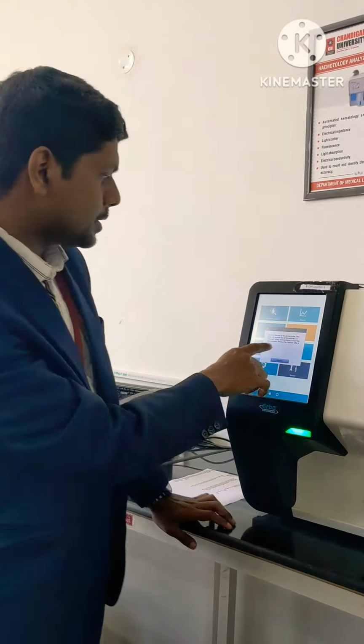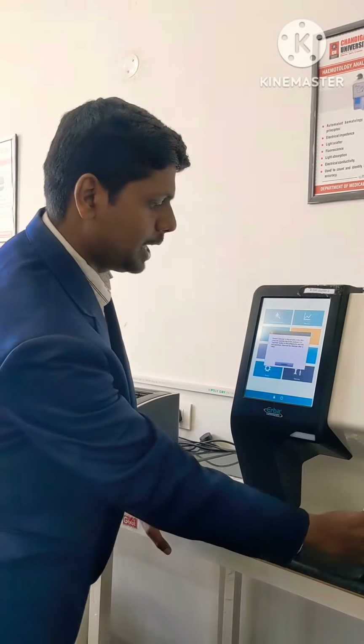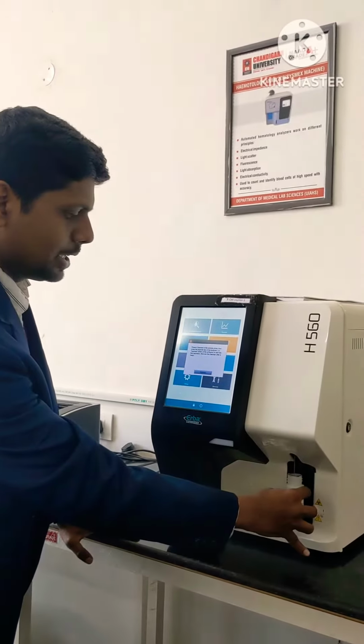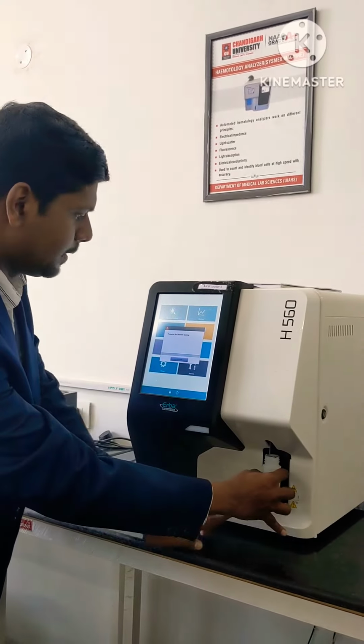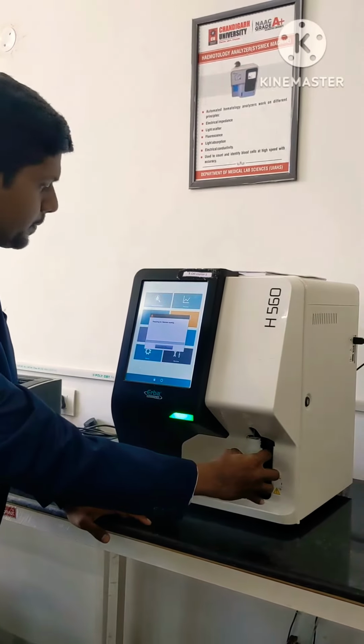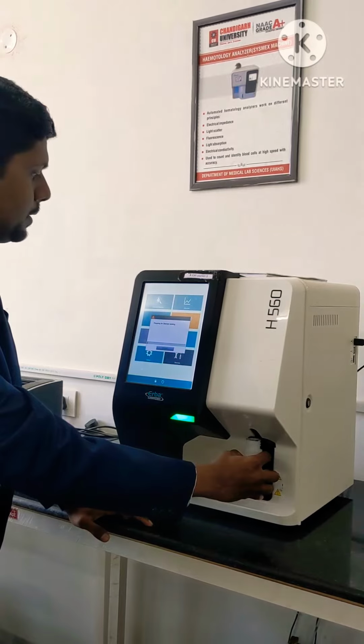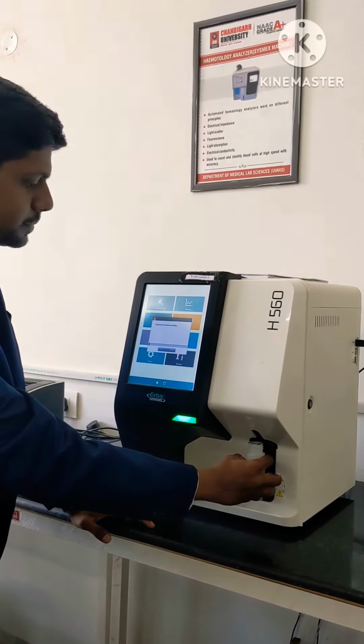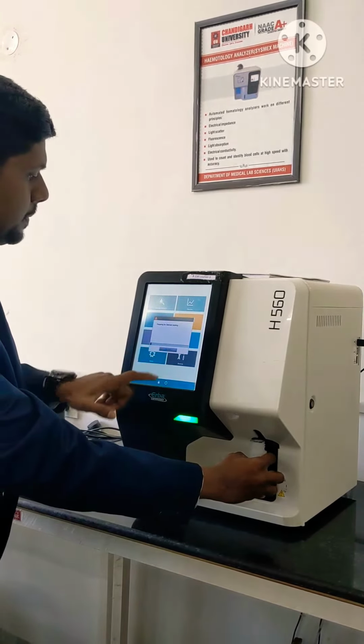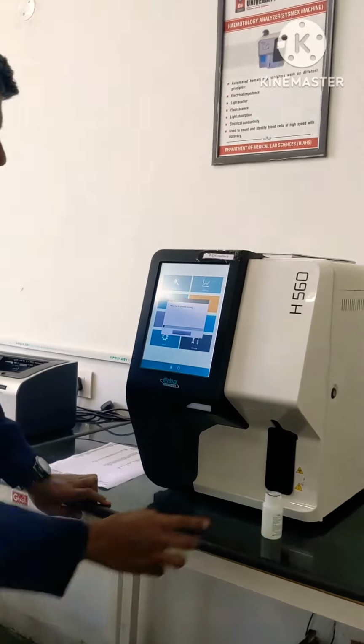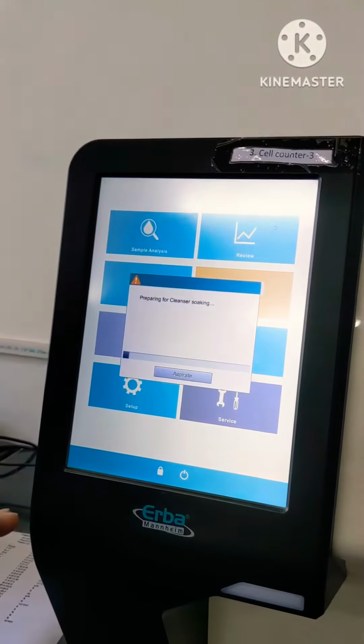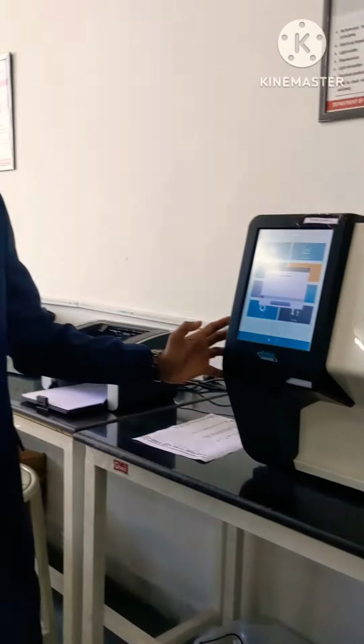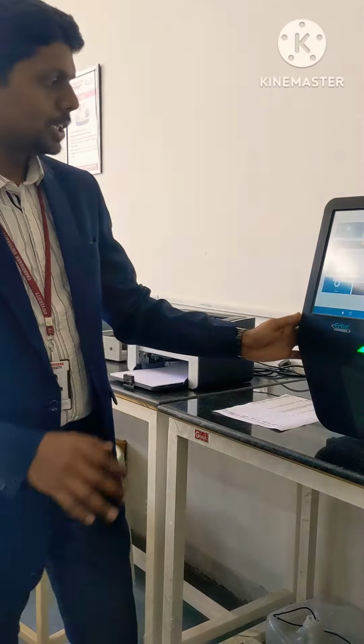Then the machine will ask to present the sample to the aspiration probe. So you need to give the sample to the aspiration probe like this. So once you have given it and click this one, it will start aspirating and it is taking the sample. So preparing for soaking. So it's doing the aspiration. Eventually after a few minutes the machine will shut down automatically, and you need not panic during this procedure. So this is the process of shutting down the machine. Thank you very much.